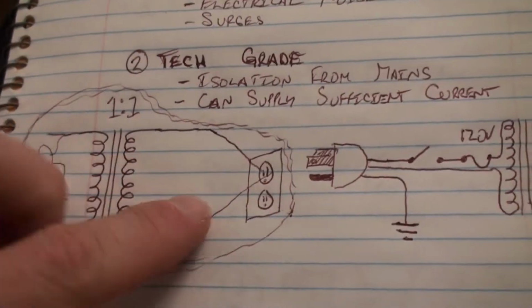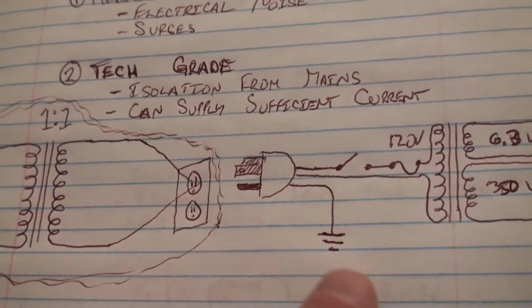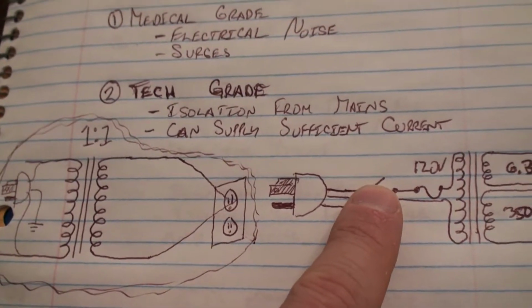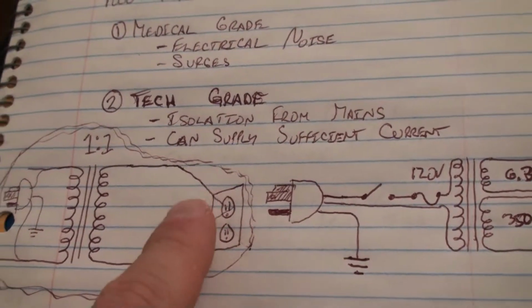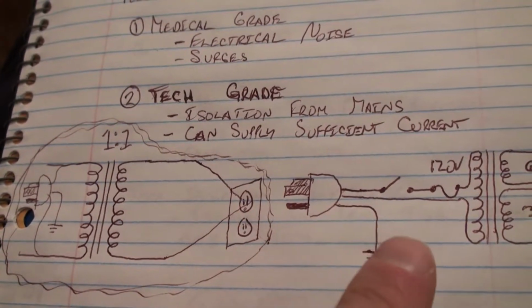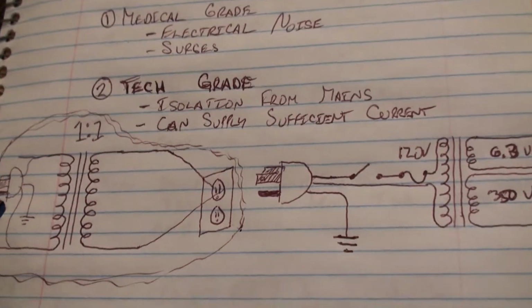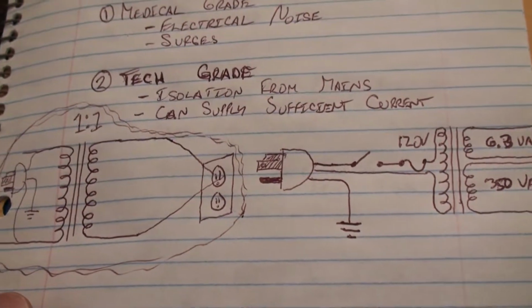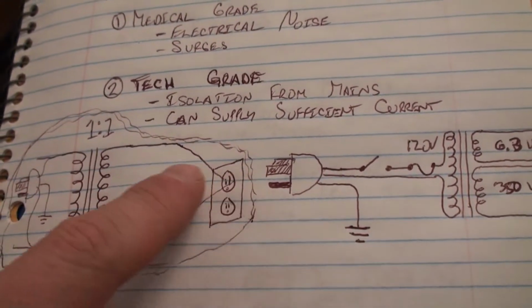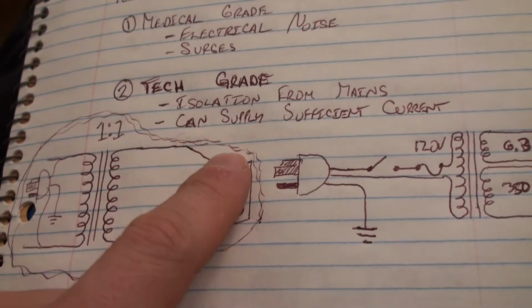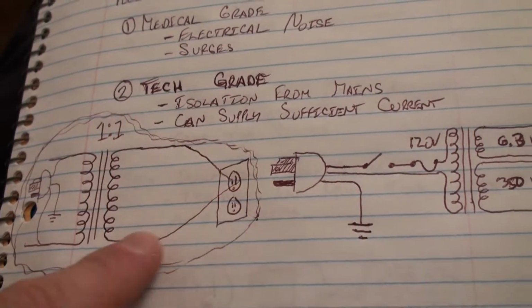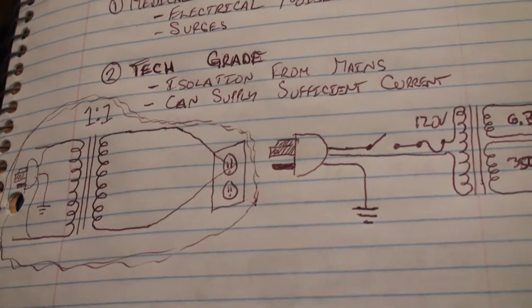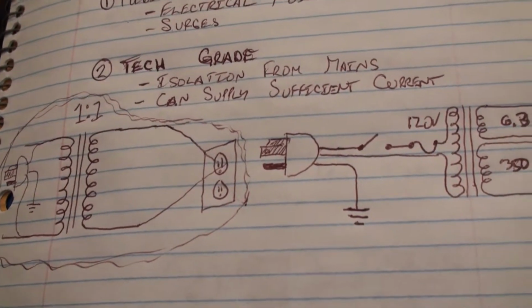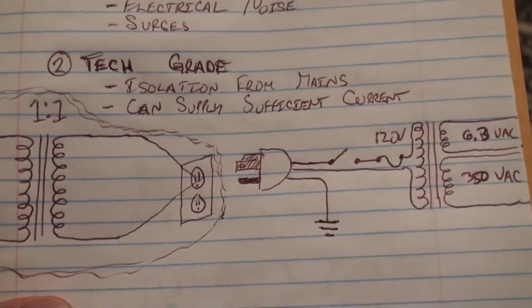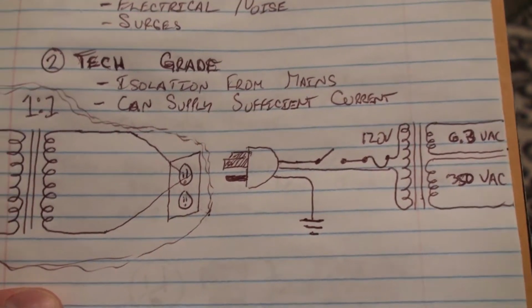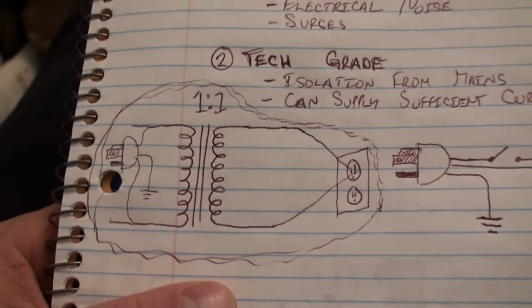So it makes the primary side such that I can actually touch the hot here when I'm plugged into the isolation transformer, and there's no reason for the electricity to want to go through my finger into the ground, because the only thing the power wants to do is go through here and come back. It doesn't want to go through you. I mean, again, you still will get a shock, a capacitive type of shock, but it won't be lethal. I'm trying to figure out if there's anything I'm missing here.